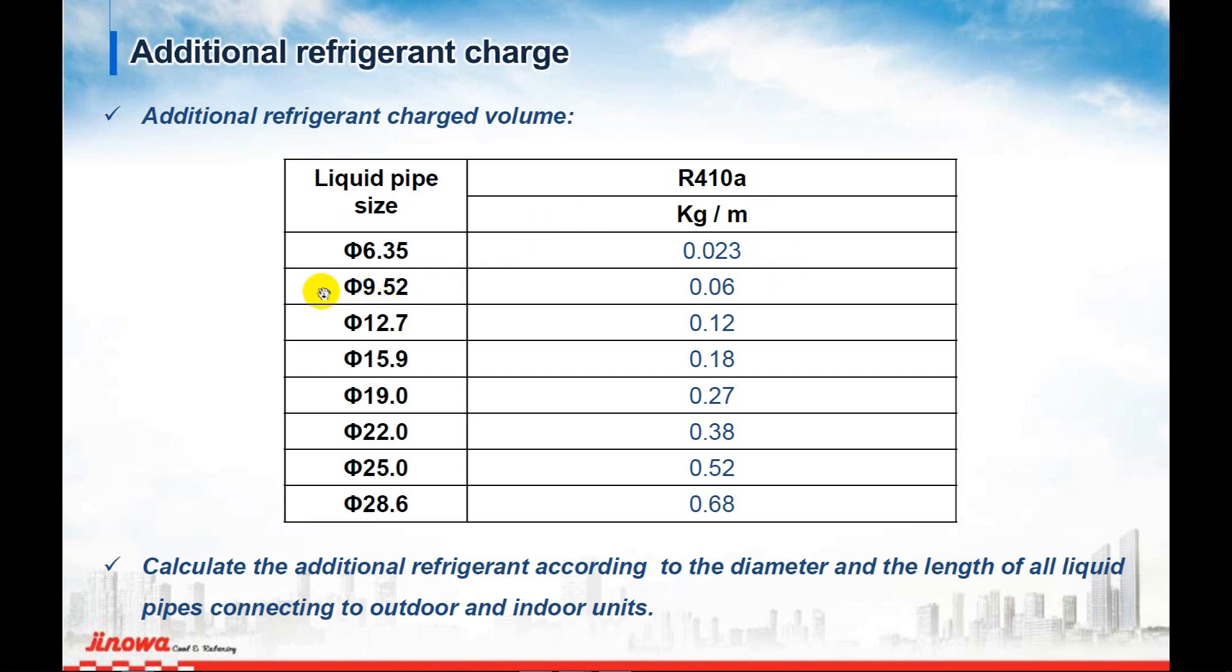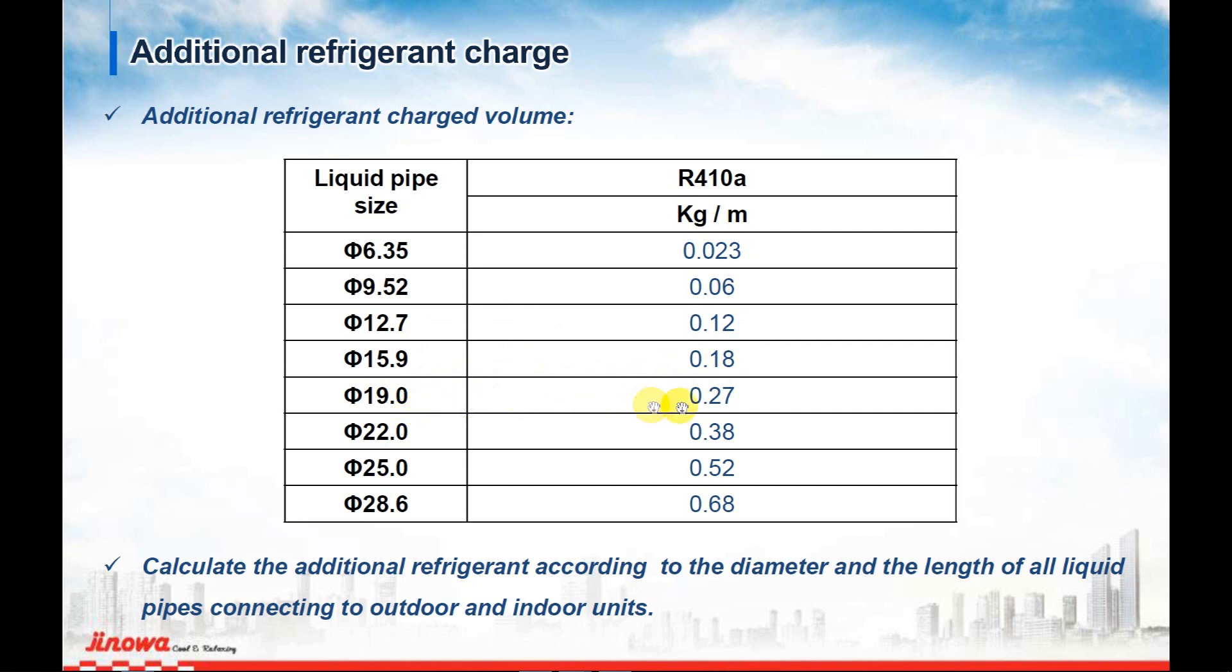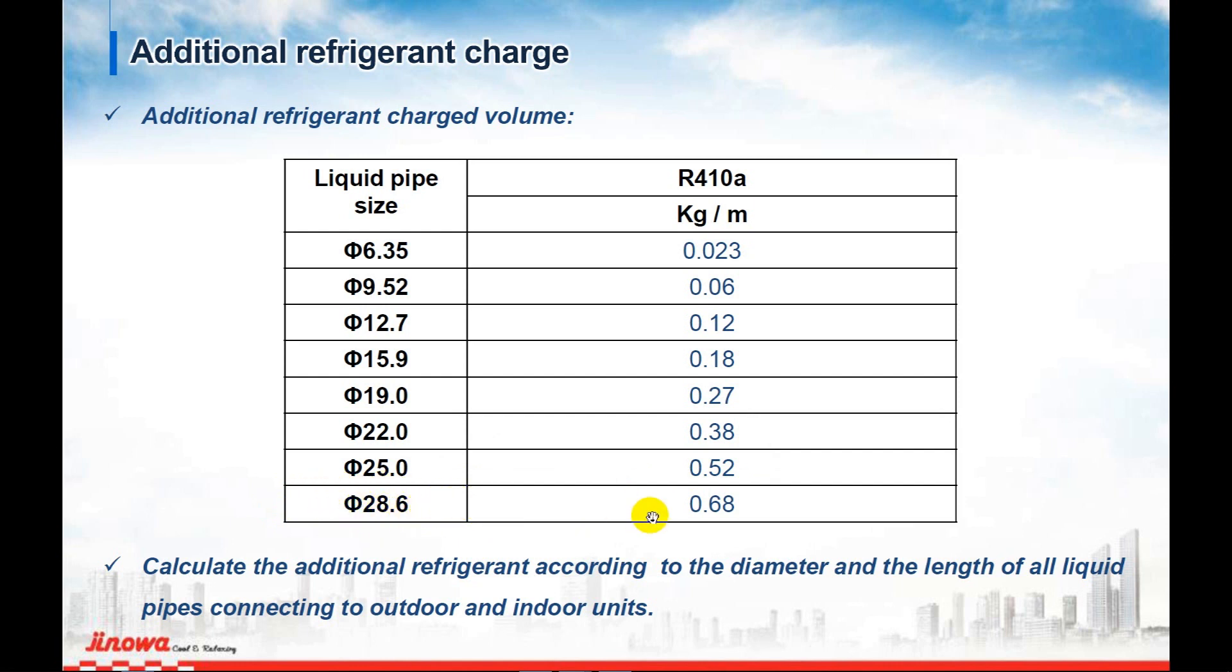For size 9.52, you add 0.06. 12.7 is 0.12, 15.9 is 0.18, 19 is 0.27, 22 is 0.38, 25 is 0.52, and the final one, the biggest, is 28.6 at 0.68 kilograms per meter.